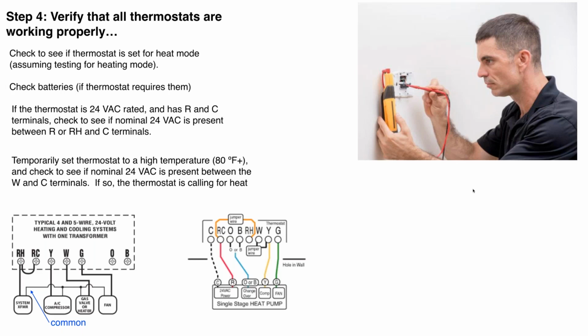We've got a local HVAC firm that advertises that one of their clients paid $200 to have a technician come out and change one of the AA batteries in their thermostat. So obviously check the batteries. Now, if it's a 24-volt rated thermostat and you have an R and a C terminal in the thermostat, put your meter on it, see if you've got a nominal 24 volts. It might be 26 volts, it might be 23 volts, but nominal 24.